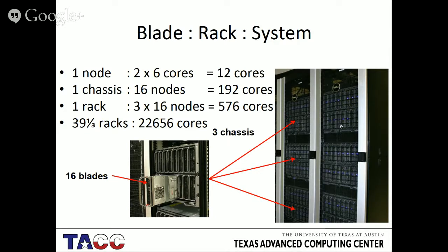Notice how these racks look a little empty. There's a lot of space at the top and space in between the chassis. This is because they create so much heat and such a small footprint that we could not fill the rack completely up because it would overheat the room too much. And so we purposely have the racks a little bit empty so that our power density is such that we can cool it.